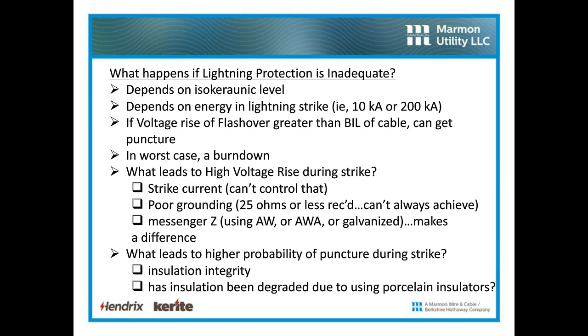But what leads to a higher probability of a puncture during a strike is poor insulation integrity: if that cable has been missized, if you're using a 15 kV cable at 25 kV, et cetera, or if the insulation has been degraded due to using porcelain insulators or porcelain spacers.